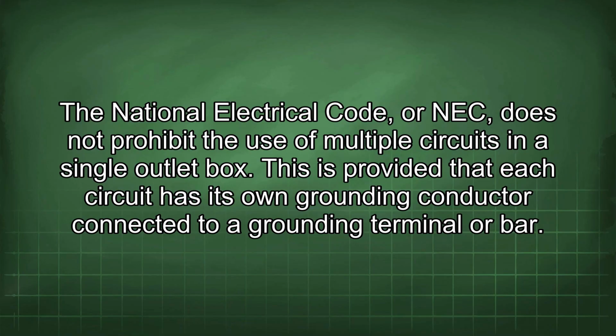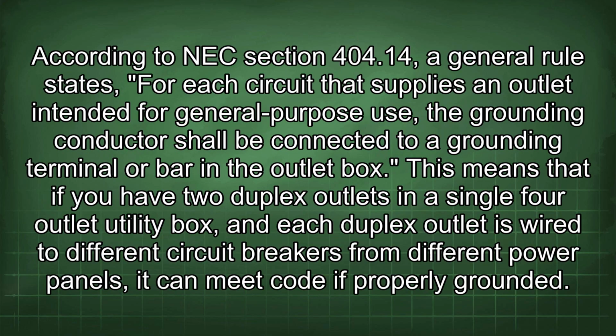The National Electrical Code, or NEC, does not prohibit the use of multiple circuits in a single outlet box, provided that each circuit has its own grounding conductor connected to a grounding terminal or bar. According to NEC Section 404.14, a general rule states that for each circuit that supplies an outlet intended for general purpose use, the grounding conductor shall be connected to a grounding terminal or bar in the outlet box.